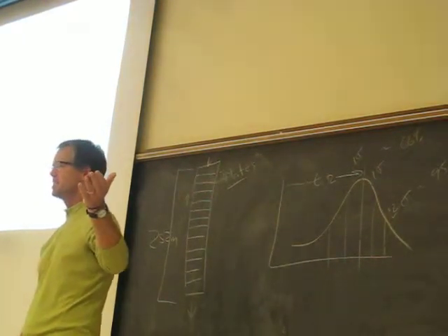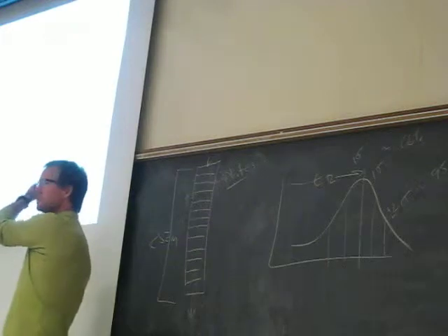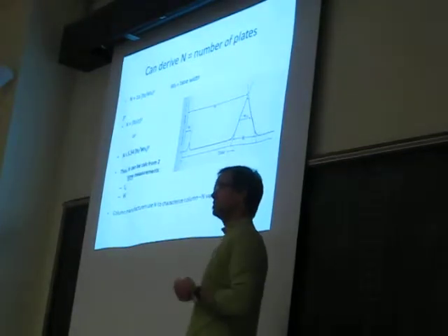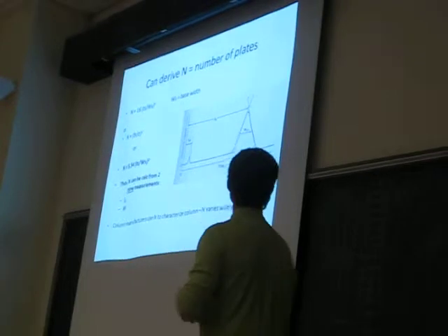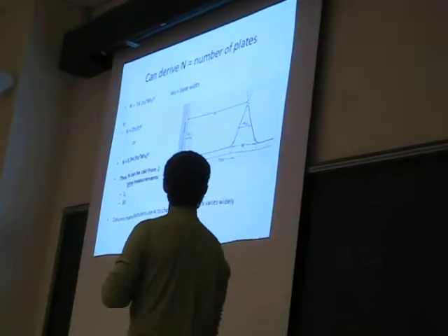For all I know, there's a default value in there of 15 centimeters, right? Well, maybe each value is wrong. That's something you can check, right? So I would calculate for a couple different peaks what you get for the theoretical plate height and compare that to what the software tells you. And then we can actually find out if there is somewhere in the software where the value for the column needs to be changed.